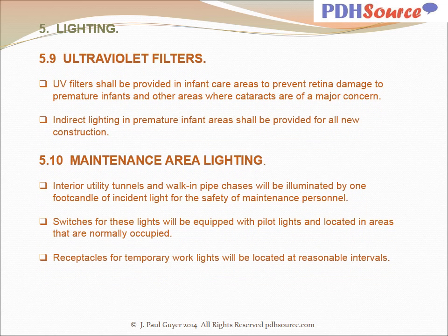Ultraviolet filters shall be provided in infant care areas to prevent retina damage to premature infants and other areas where cataracts are of a major concern. Indirect lighting in premature infant areas shall be provided for all new construction. Interior utility tunnels and walk-in pipe chases will be illuminated by 1 footcandle of incident light for the safety of maintenance personnel. Switches for these lights will be equipped with pilot lights and located in areas that are normally occupied. Receptacles for temporary work lights will be located at reasonable intervals.